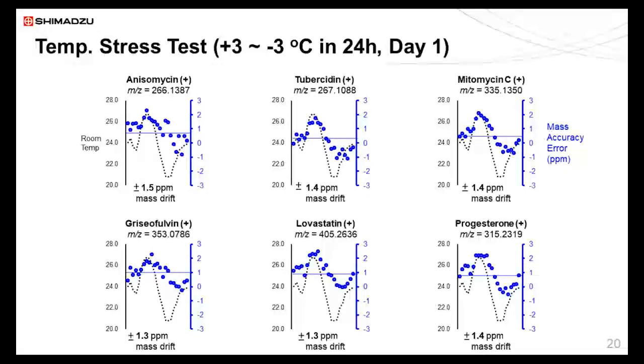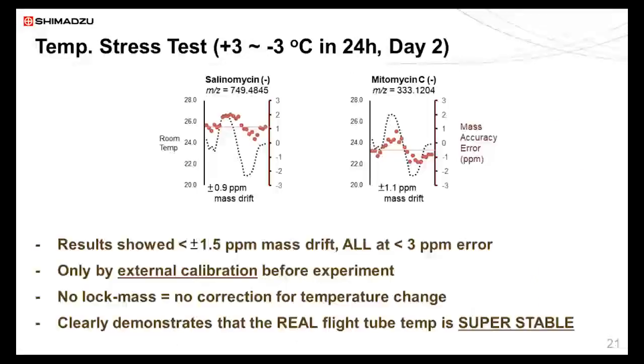So we could see clearly that the blue mass accuracy trace follows exactly the trend of the black dotted temperature trace. And the extent of mass drift, we've seen that it's within plus or minus 1.5 ppm. And similarly for the negative mode, 0.9 ppm mass drift, 1.1 ppm mass drift. So results showed that all the data in this stressed environment, we observed less than 1.5 ppm mass drift, and all the data points fell under 3 ppm mass error. And this is only by one single external calibration conducted before the experiment, and no lock mass was used. And this clearly demonstrates that the flight tube temperature is super stable. So everything's under control.